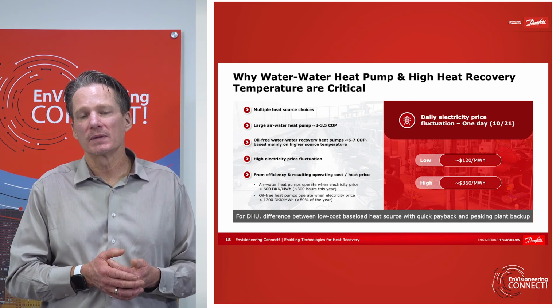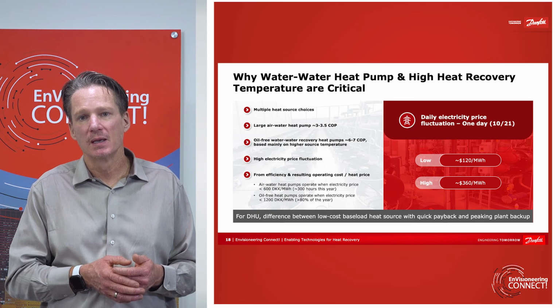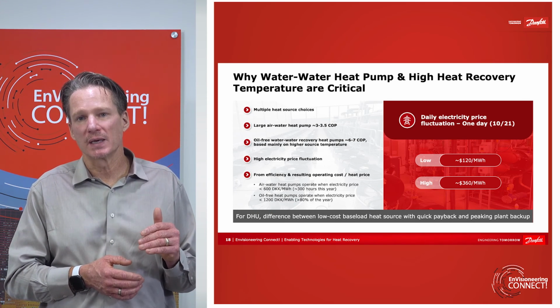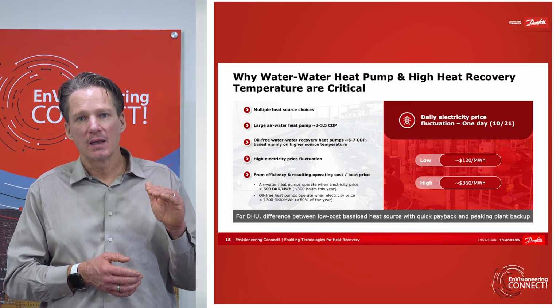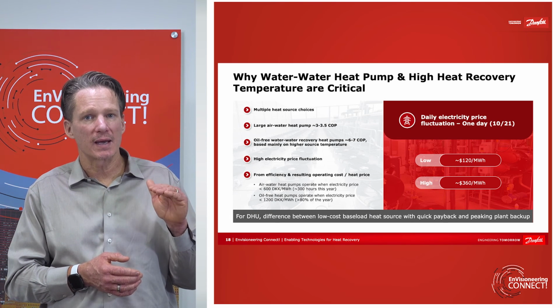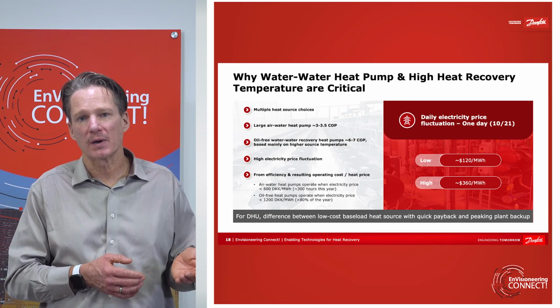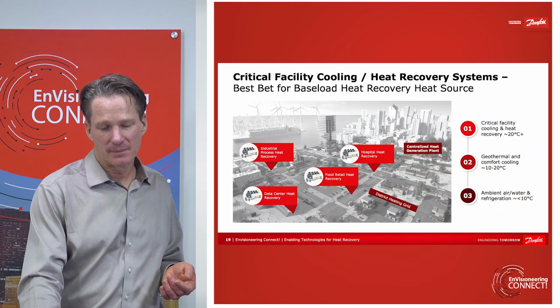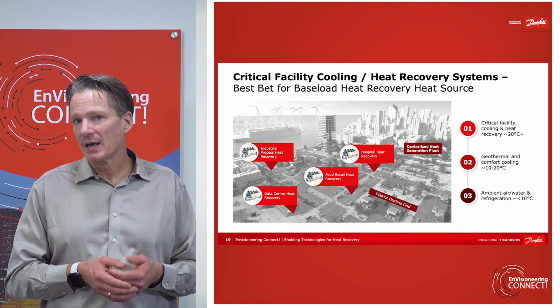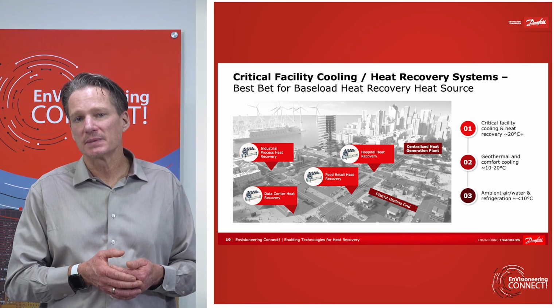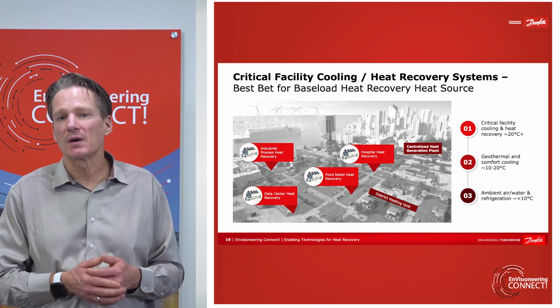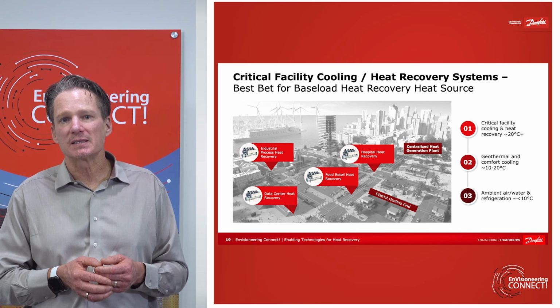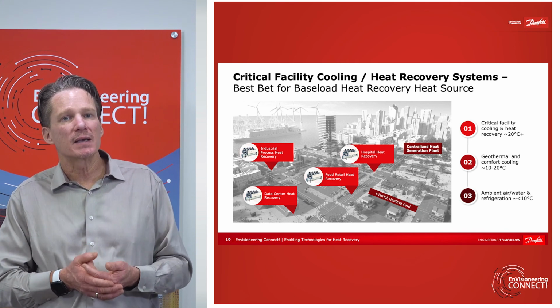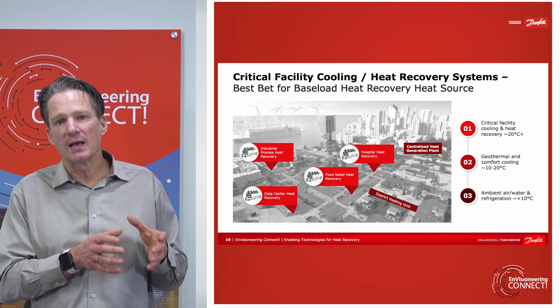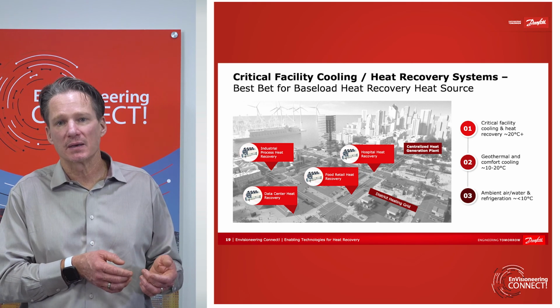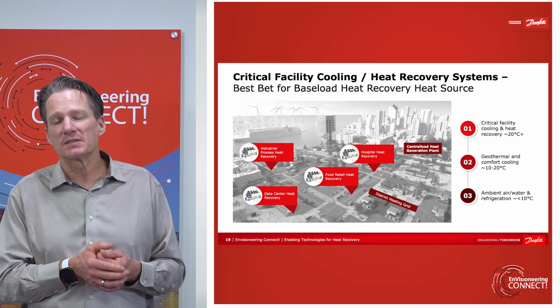That makes it even more important for the heat recovery heat pump system that you implement to be extremely efficient, because it makes it resilient to that price fluctuation. In other words, if you're operating at a 7 COP, then the energy cost that you can absorb with that is significantly different than, for example, an air-to-water heat pump operating at a 2.5 to 3 COP. So again, this is a summary of the learnings. Critical facility cooling systems and heat recovery from them are the best opportunity. Geothermal and comfort cooling systems, based also on our experience over the last couple of years, are generally what we consider to be the second tier opportunity. This is where most people are focused today, because they understand that the ambient air and water centralized heat recovery heat pump systems tend to be relatively inefficient and are not near as resilient to those price fluctuations.